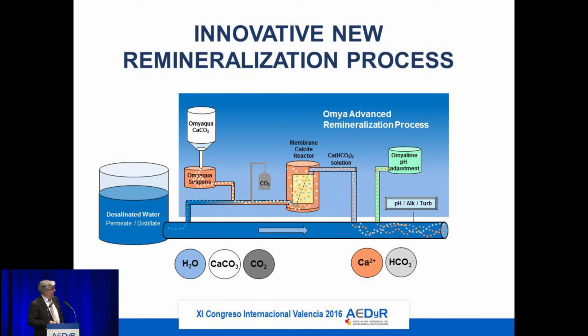So actually, there is a new process developed which is quite similar in setup, but has some very specific developments which are totally new to this market. As I said before, the curve was showing micronized calcium carbonate. So we add calcium carbonate in a slurry makedown system, coming from a bypass. The slurry makedown with calcium carbonate feeds into a so-called membrane calcite reactor. In this membrane calcite reactor, we have...